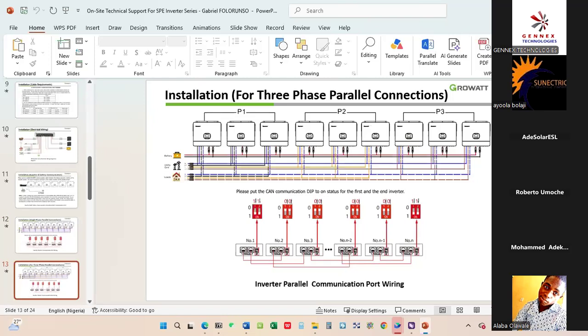I hope you get that message now. So this inverter, once you don't turn on all your breakers at the same time, it will call a warning sign. That's why when installing, we need to find a way to overwrite that issue. One example: instead of using a 2-pole breaker, you can explore a 4-pole breaker, so that each inverter is not separate but becomes 1. That way, when you lift the lever up, everything gets to the inverter simultaneously, with no time lag.